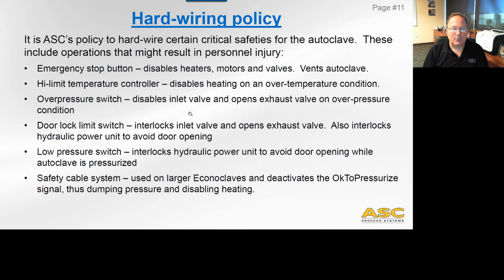So that's a requirement on all autoclaves. Over-pressure switch, that's a pressure switch which basically is set about 5 psi over maximum operating pressure, and that is going to, again, trigger a relay which interfaces and is fed into the PLC and to CPC. That's going to disable the inlet valve and open the exhaust valve. And door lock limit switch, that's the door bar lock. Interlocks inlet valve and opens exhaust valve, also interlocks hydraulic power unit to avoid door opening when it's locked.